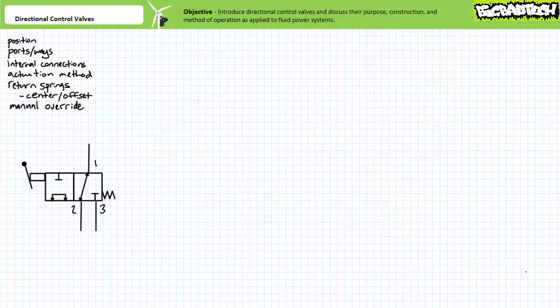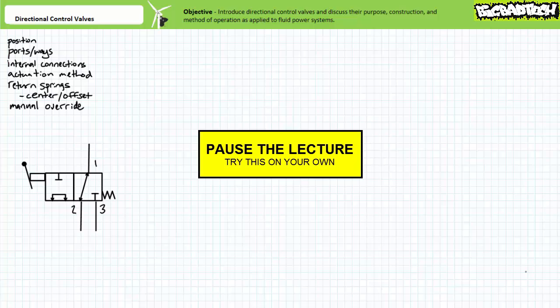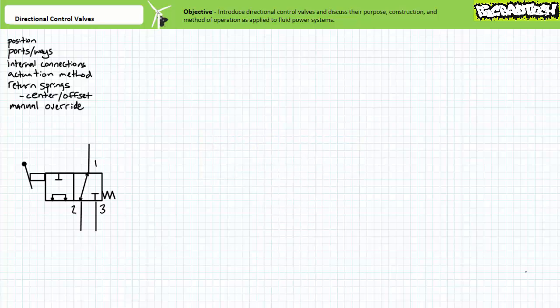Let's again put your newfound knowledge of directional control valves to the test. Pause the lecture and see if you can determine the number of positions, the number of ways, the actuation method, and the deactivated state of this directional control valve. This is a two-position, three-way, manually actuated directional control valve, spring offset to a deactivated position that blocks flow at port three and allows bidirectional flow from one to two. In its activated state, it allows bidirectional flow from two to three and blocks flow at one.